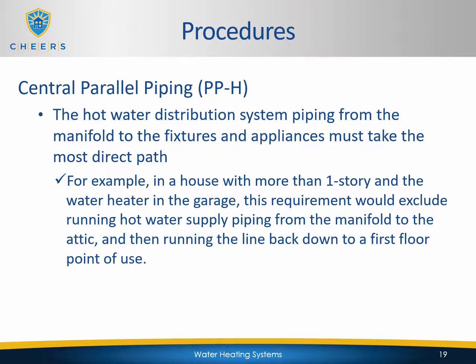The hot water distribution system piping from the manifold to the fixtures and appliance must take the most direct path. For example, in a house with more than one story and the water heater in the garage, this requirement would exclude running hot water supply piping from the manifold to the attic and then running the line back down to a first floor point of use. The lines have to be the most direct, shortest as possible.